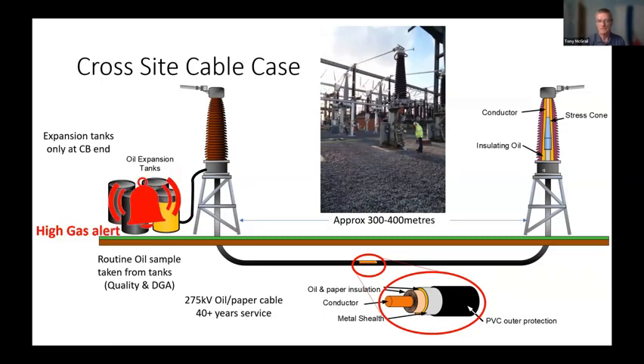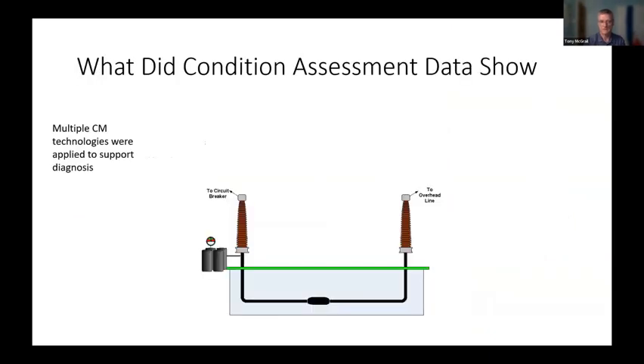The gas alert comes in. So this is from a routine sample. We did have cables where we had online dissolved gas analysis. We would use either hydrogen-only monitors or composite gas monitors, depending on what we were thinking the cable was likely to fail, what the mode would be. So we had expectations for each cable, what the likely failure mode would be. We had plans for reacting to those. Next one, please.